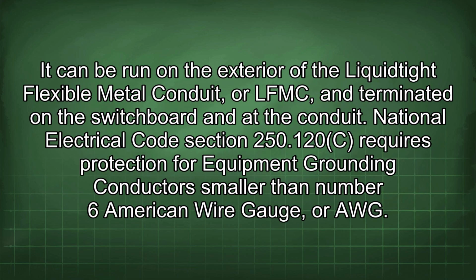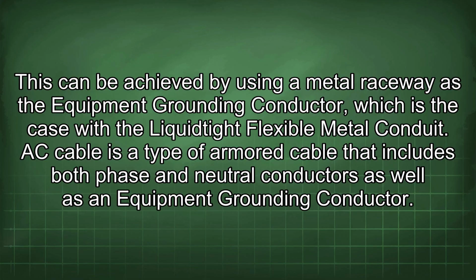It can be run on the exterior of a Liquidtight Flexible Metal Conduit, or LFMC, and terminated on the switchboard end of the conduit. National Electrical Code section 250.120(C) requires protection for equipment grounding conductors smaller than number 6 American wire gauge, or AWG. This can be achieved by using a metal raceway as the equipment grounding conductor, which is the case with the Liquidtight Flexible Metal Conduit.